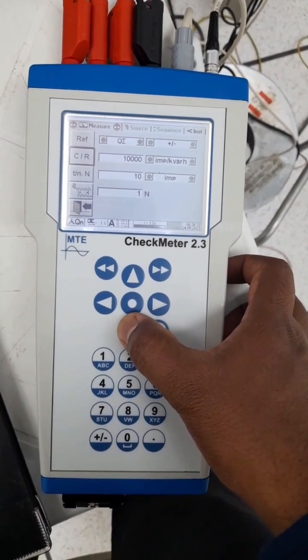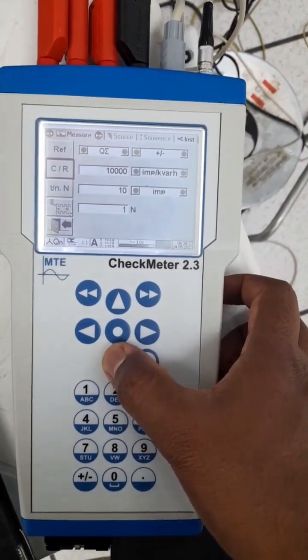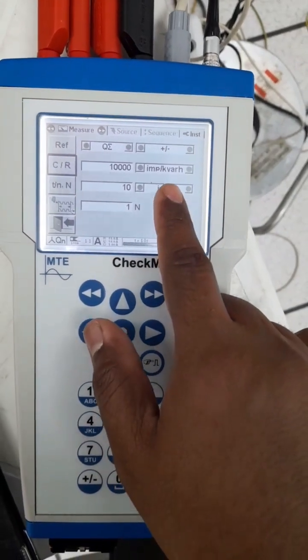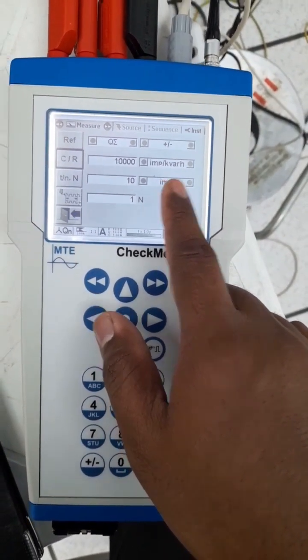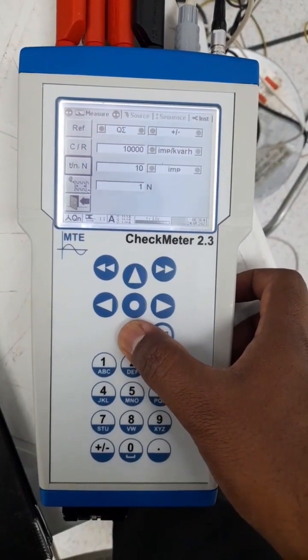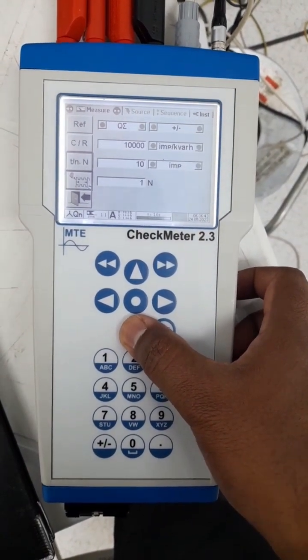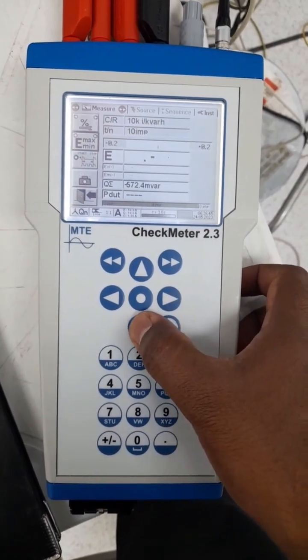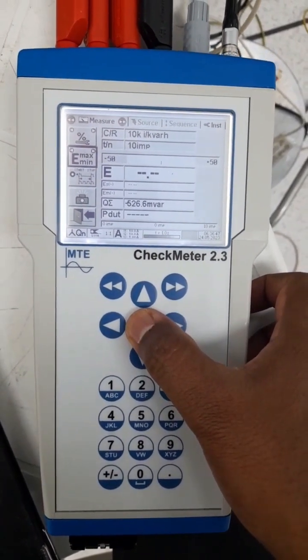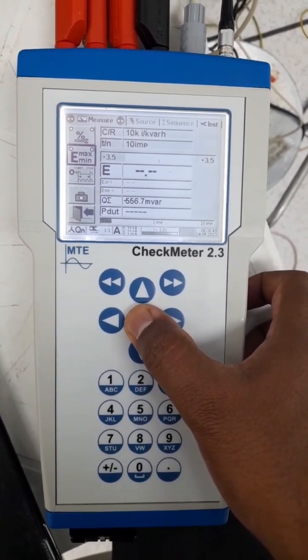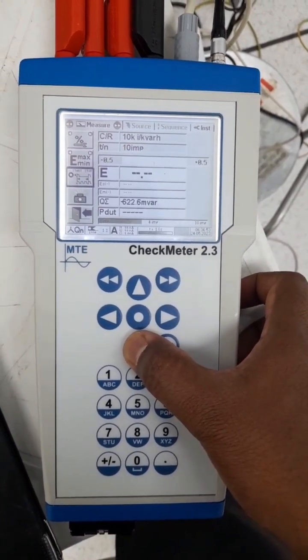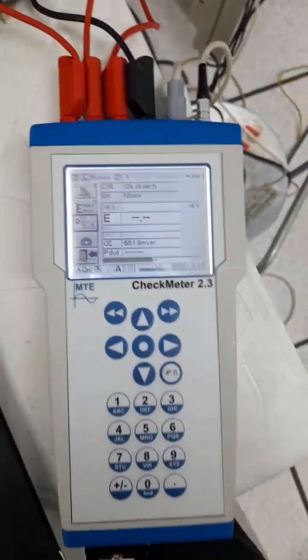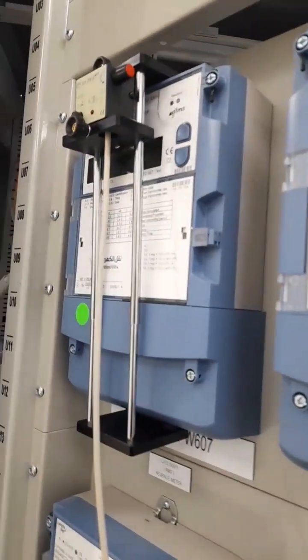The constant remains the same. See, automatically this option gets changed to impulse per kVArh. Here also I just put 10 pulse and come down. My accuracy was 0.5 for reactive energy, so I'm going to change this to 0.5 and come down. Now I'm getting error because I didn't change the scanning head again, so I have to change it.